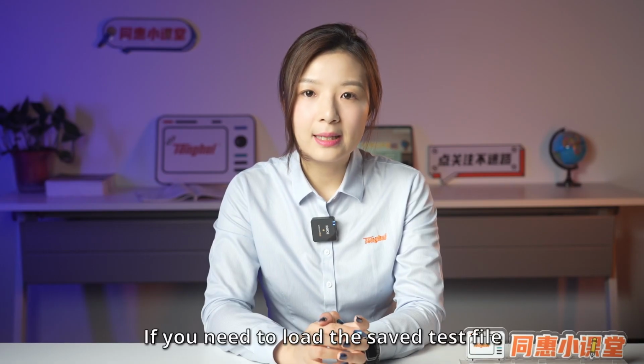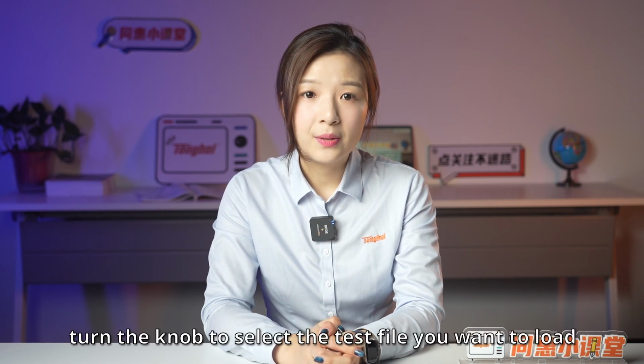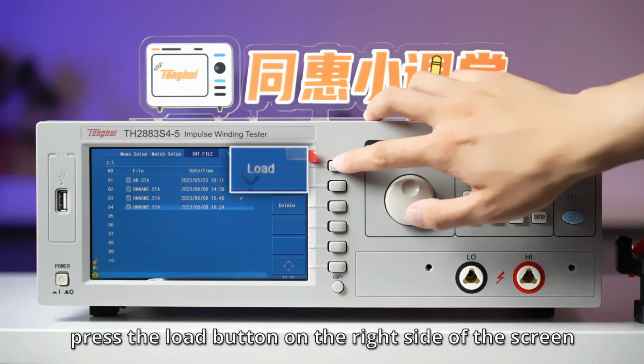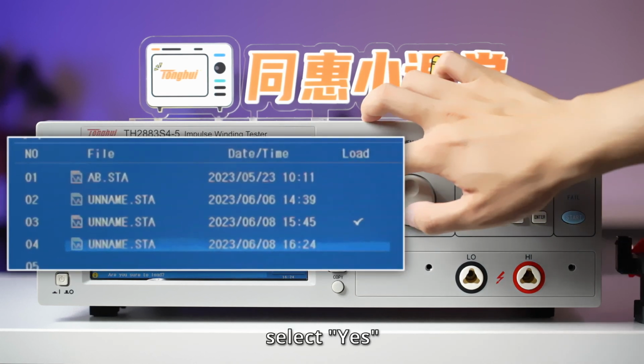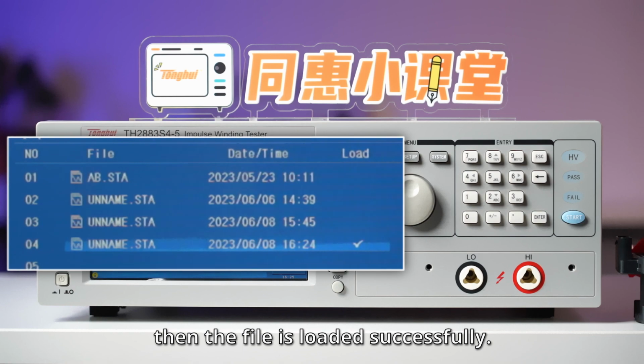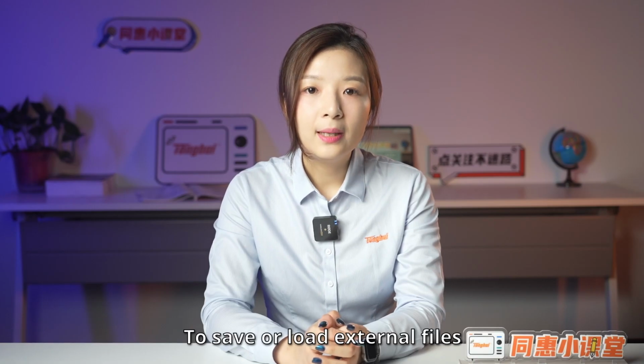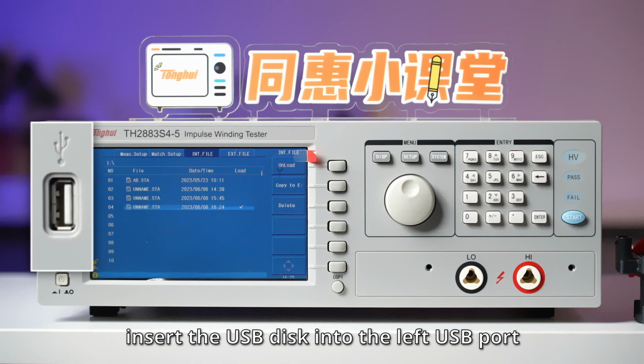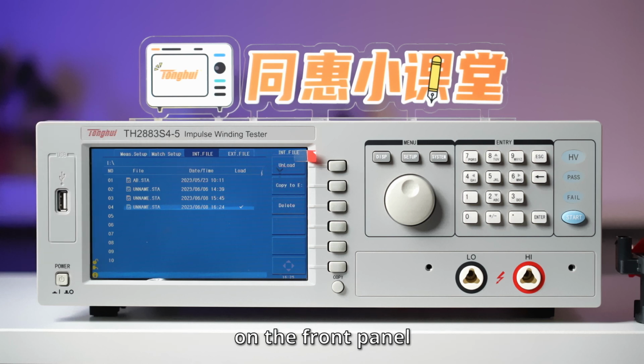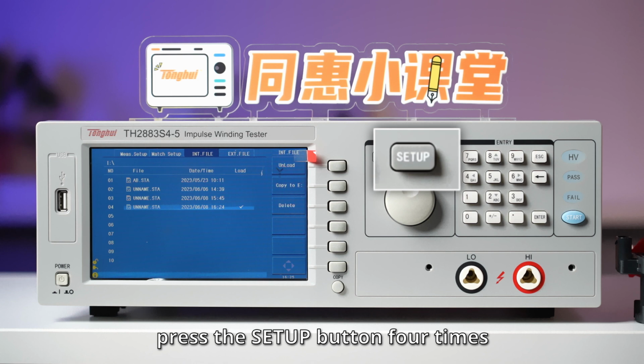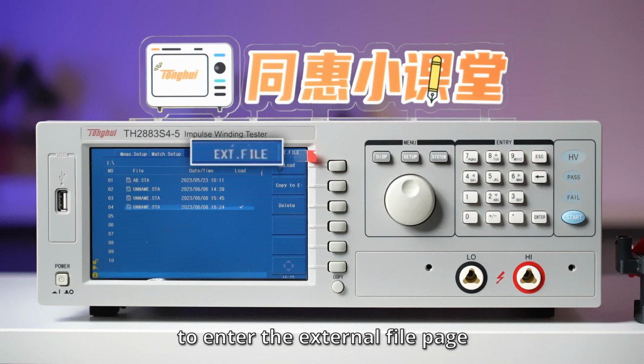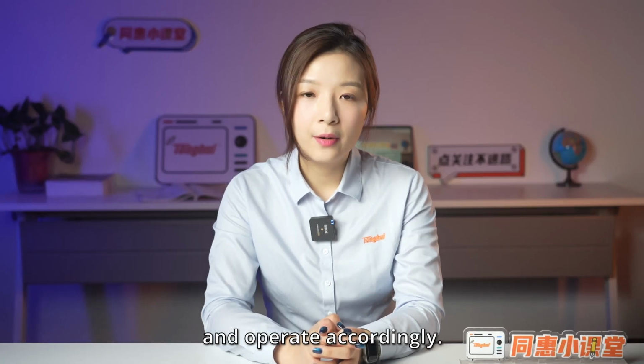If you need to load the saved test file, turn the knob to select the test file you want to load. Press the Load button on the right side of the screen, select Yes, and then the file is loaded successfully. To save or load external files, insert the USB disk into the left USB port on the front panel. Press the Setup button 4 times to enter the external file page and operate accordingly.